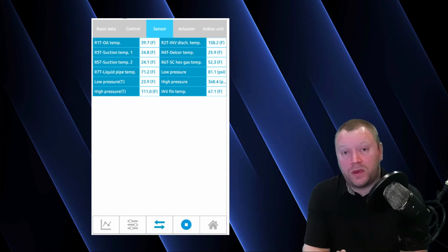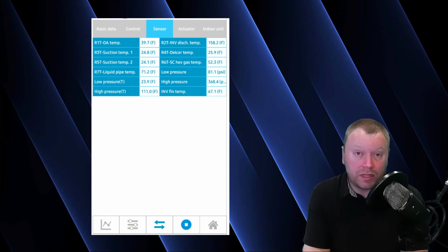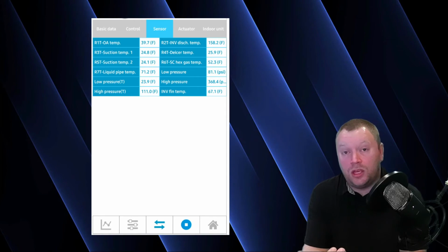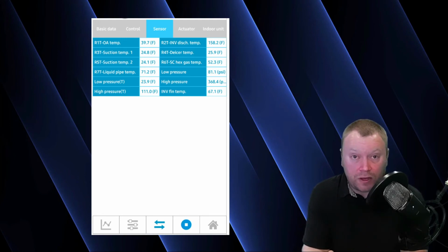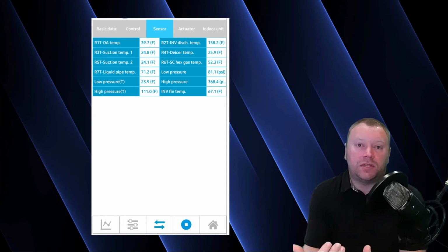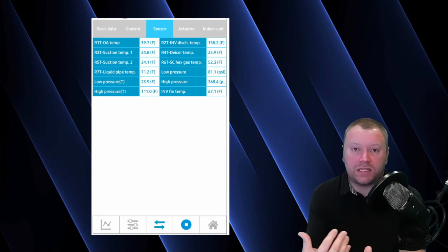I always recommend when guys are hooking up Dchecker that you run the system for 20 minutes before you analyze any of your data. Because let's say you're starting from an off position, right? So you turn the system off, you plug in your Dchecker, then you power the system back on. That was something we discussed in the how to connect your Dchecker video. So you're starting from an off position. That unit's going to have a ton of liquid sitting in the heat exchanger, and it's going to take some time to process that loop.